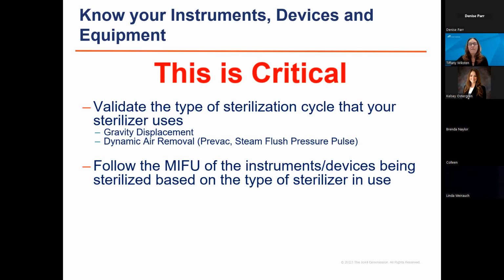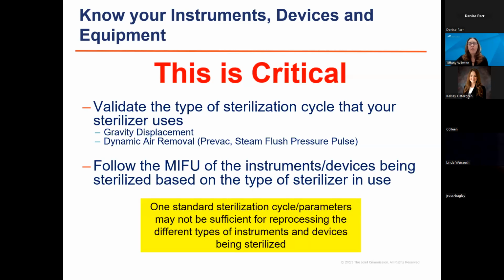So gravity displacement sterilizer, time and temperature could be vastly different than the time and temperature requirement for dynamic air removal. So you have to make sure that you follow the manufacturer's instructions for use on the instruments or devices being sterilized based on the type of sterilizer in use. And I want you to keep in mind that one standard sterilization cycle and parameter may not be sufficient for reprocessing the different types of instruments and devices being sterilized, right? So if you have a small wound care clinic that has simple stainless steel surgical instruments all from one manufacturer, one sterilization cycle time and temperature might be okay. But if you're in a dental setting or in another setting that uses a wide variety of instruments, you might need to have several different sterilization cycles and parameters in use.